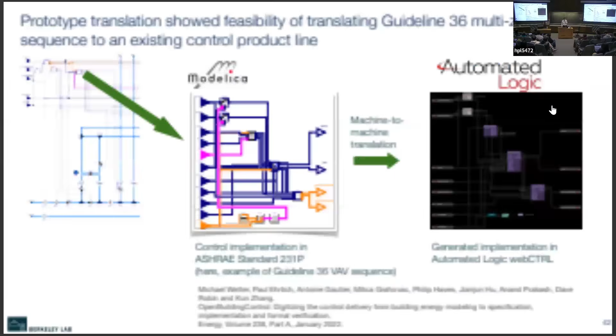We implemented the Modelica model based on Guideline 36 for a VAV sequence, and translated that to Automated Logic. What you see in the middle of the graphic is a subset of this control sequence, with two PI controllers on top, and the same controllers translated into the ALC implementation, along with this nested controller, for example, for the damper controllers.